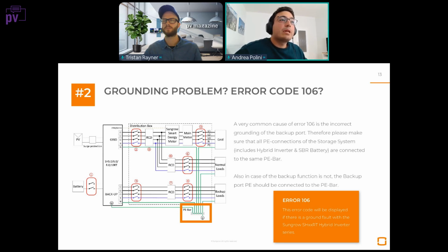And it is very important that basically all of this is grounded to the same point. So not only the inverter chassis, as we can see on the bottom, but also the PE for the 2 AC connectors should come to the grounding side.